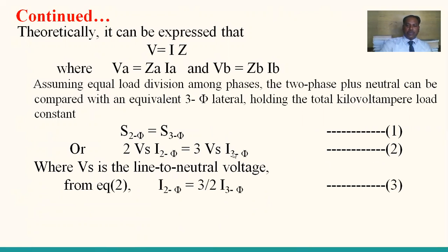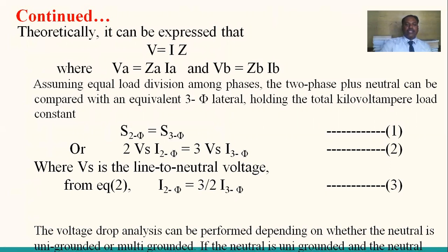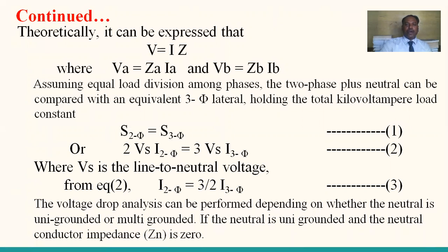And from equation number 2, this can be simplified. Simply Vs cancel here, and I2 phase is equal to 3 by 2 times I3 phase. This is equation number 3. And similarly, the voltage drop analysis can be performed. After finding the relation between both currents, we are going to do the voltage drop analysis. So the voltage drop analysis can be performed depending on whether the neutral is uni-grounded or multi-grounded.